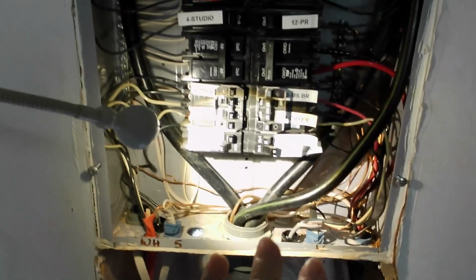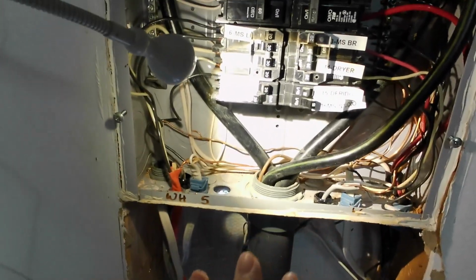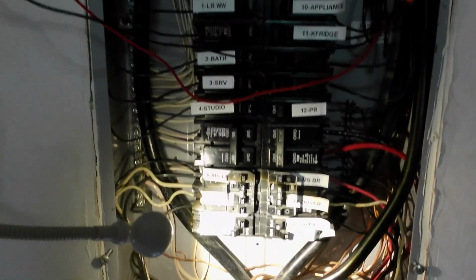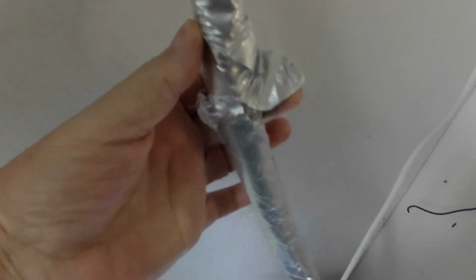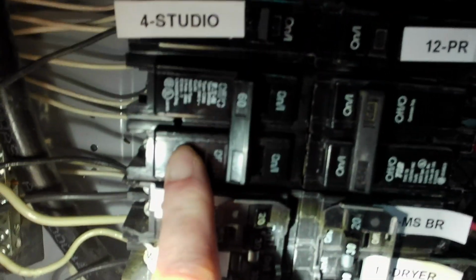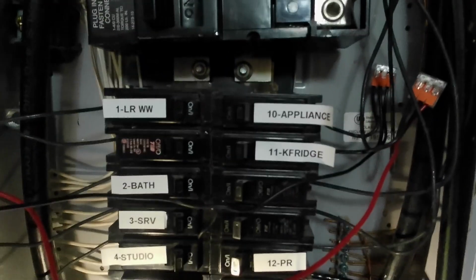So this panel now needs to be replaced, but I don't have the money to do it right now, so I'm making do with what I got, and as soon as we have the finances available, we'll replace the panel. This cable will hold 100 amps, so I could have this going over to my solar at 100 amps, but I've decided to limit it and only put a 60 amp breaker on there. A 60 amp breaker on a number 2 aluminum wire is perfectly fine, and that way we'll limit the amount of current that can go out of there. I've labeled all my other circuits so I know where they go.